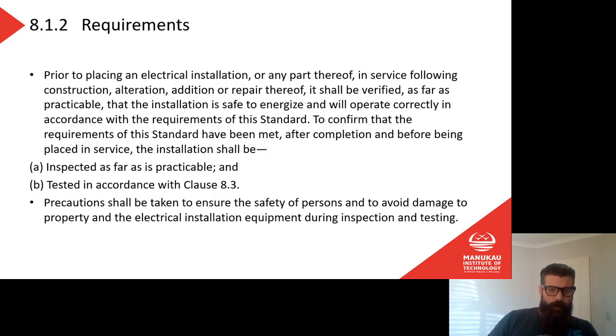To confirm that the requirements of the standard have been met, after completion, so after I've finished work, but before being placed into service, so before I turn the power on, the installation shall be inspected as far as practicable. Practicable, we've come across that word in relation to the Health and Safety at Work Act. Again, it means essentially the same thing. It means doing all the things that I can reasonably be expected to do.